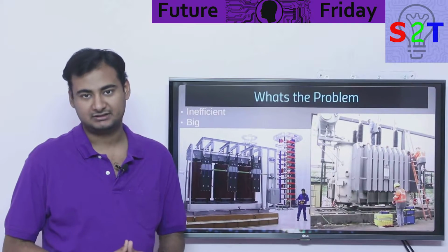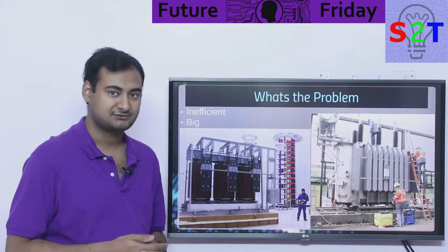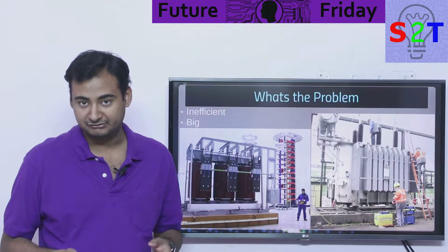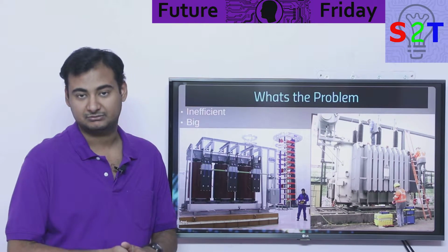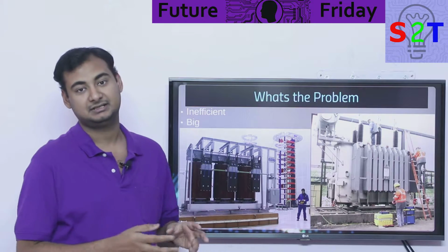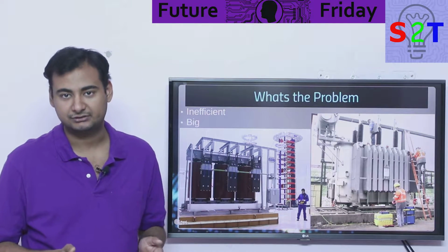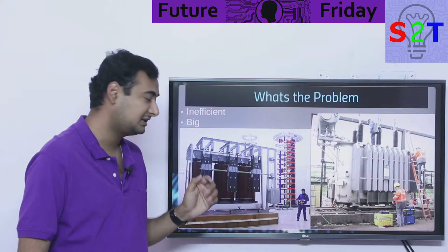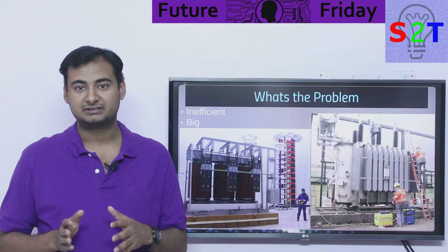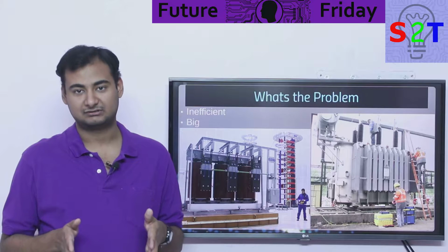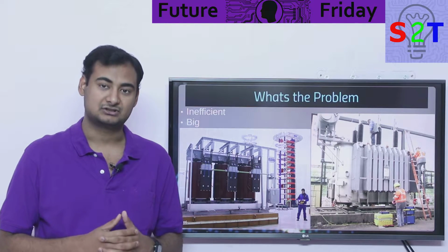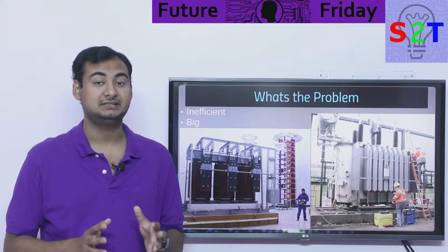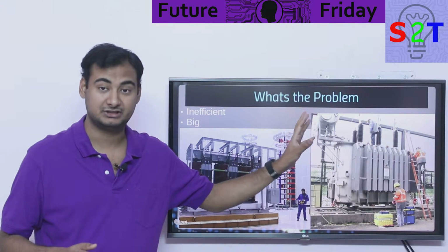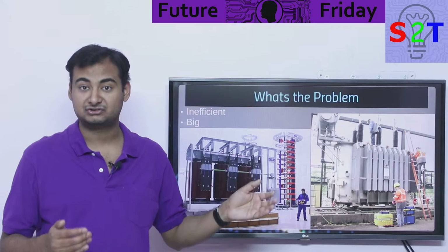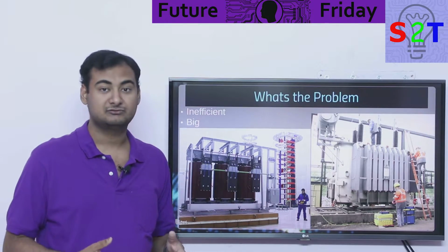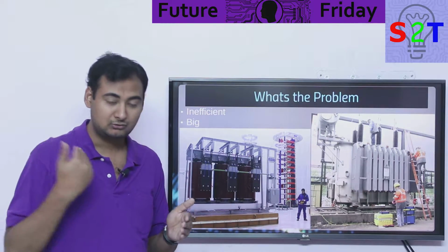First you have to understand what the problem is with our current transformer infrastructure. First, they are inefficient. As I mentioned in my last video about transformers, even though they are say 98% efficient, that's more than good enough for home application. However, when you are talking about substation scale transformers, that 2% can translate to up to 2 megawatts of loss, or sometimes even 200 megawatts of loss in case of some really big transformers. So that is a lot of energy the transformer has to dissipate, and it's also lost revenue.